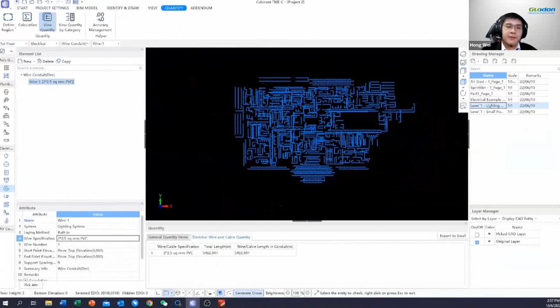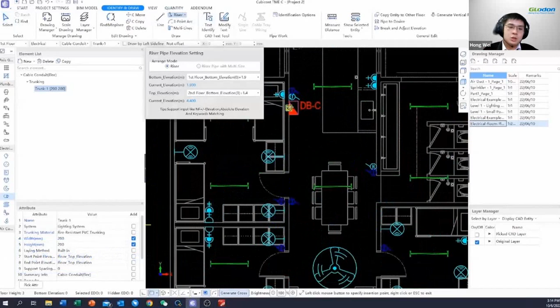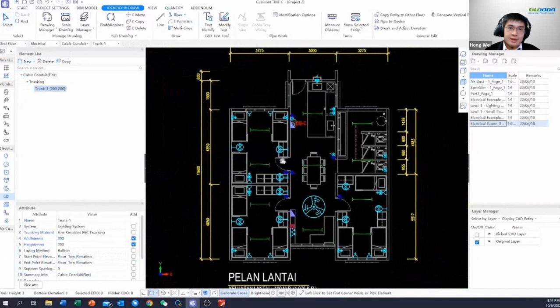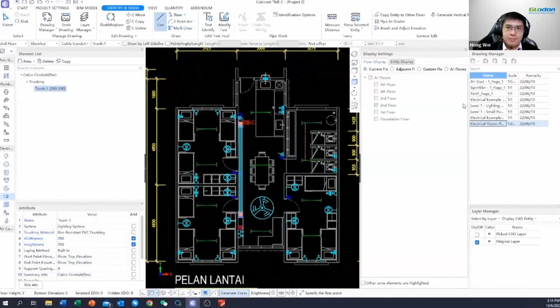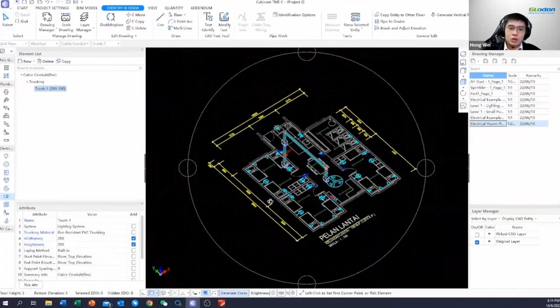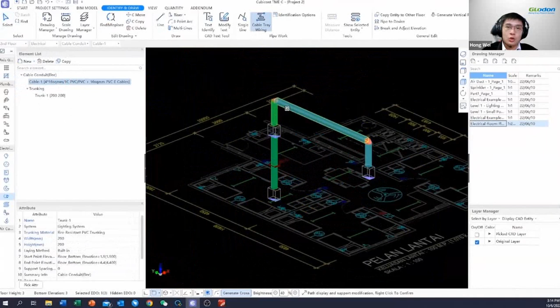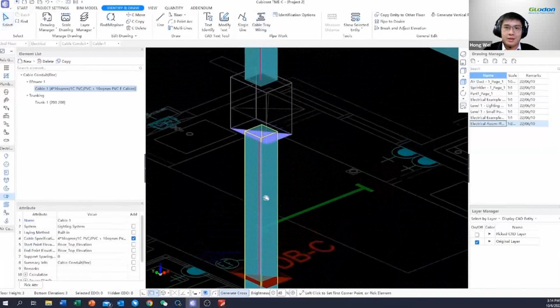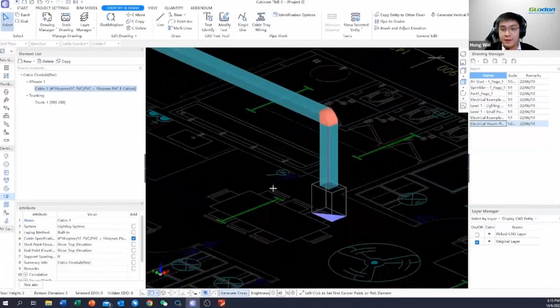And finally, let us take a look at how cross-floor cabling work is done in TMEC. First, let us construct a cable trunk that rises from the first floor to the second floor, and then connect it to a distribution box, just like that. If you view it in 3D, we can see the cable trunk is connecting the distribution box across the first and second floor. After that, we can proceed to insert the cables or wires inside the trunking by using the cable tray wiring function. Just a few clicks onto the trunking, and you can see that the wires and cables are already laid accordingly. Just like that. So once again, the whole taking off process is extremely fast and efficient. Okay?